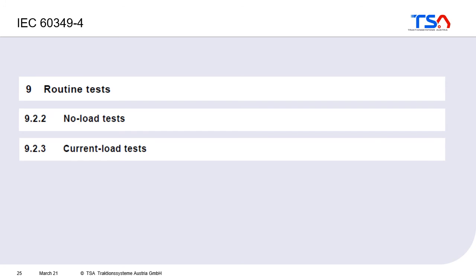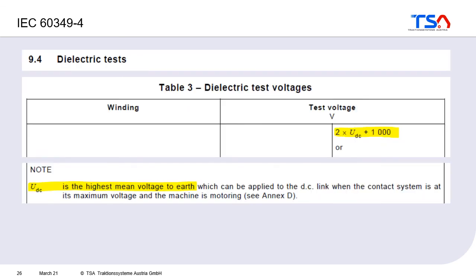During routine tests, a no-load test and a current load test are performed. For a permanent magnet machine, the no-load test measures voltage to check magnet magnetization, while the current load test gives information about machine behavior under load. The dielectric test, performed on every machine, tests insulation at two times the highest DC link voltage plus 1,000 volts. Because this test puts high stress on the insulation, it should only be performed once.